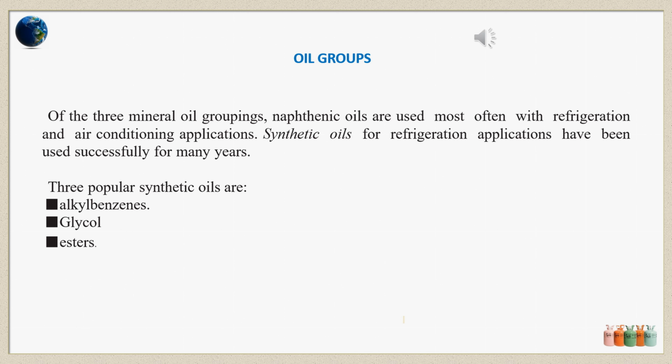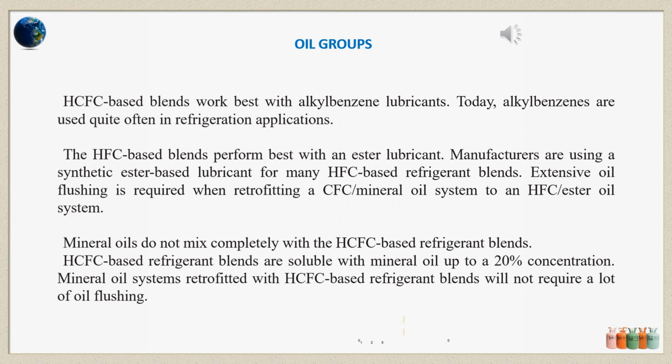Synthetic oils for refrigeration applications have been used successfully for many years. Three popular synthetic oils are alkyl benzenes, glycols, and esters. HCFC-based blends work best with alkyl benzene lubricants. Today, alkyl benzenes are used quite often in refrigeration applications.